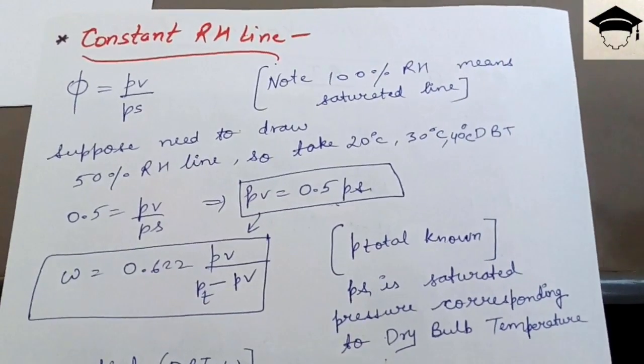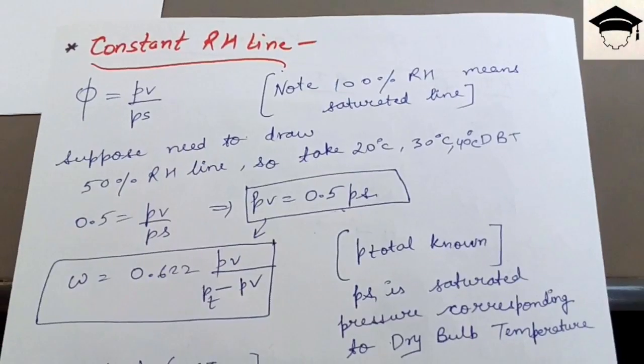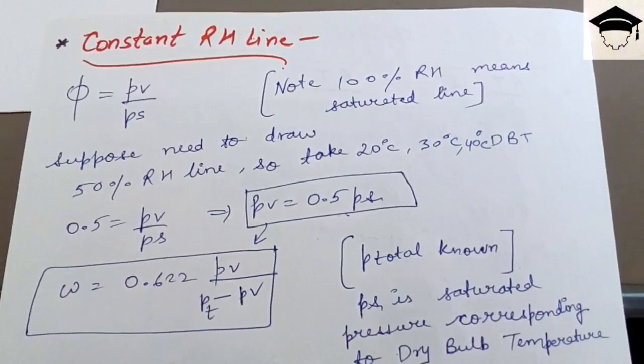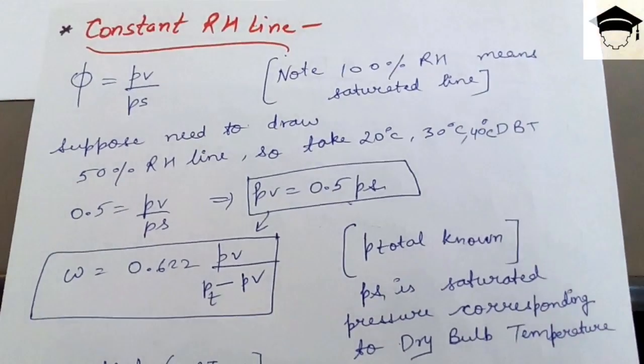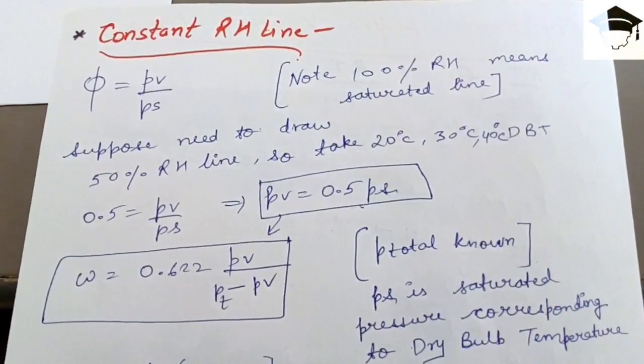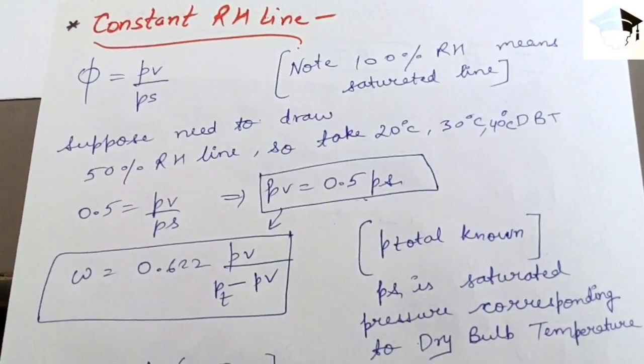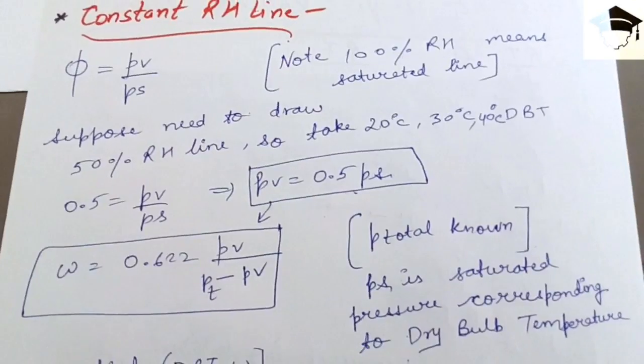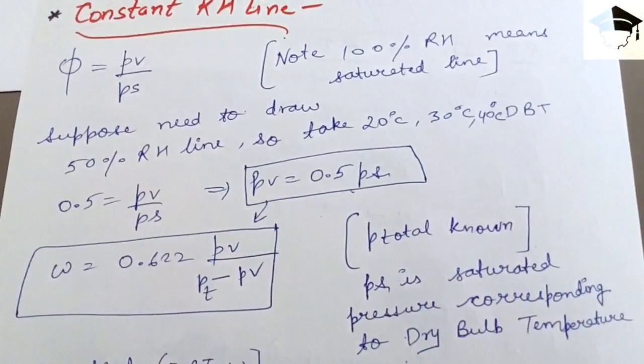To draw the 50% RH line, use the formula φ = PV / PS. Put φ = 0.5, so you get 0.5 = PV / PS, which gives PV = 0.5 × PS. Then use the formula ω = 0.622 × PV / (P_total − PV) and substitute the PV from above to find the corresponding omega value.